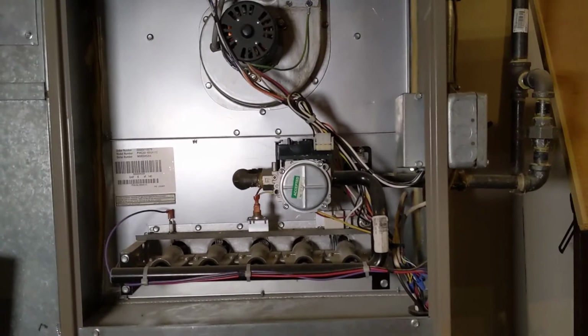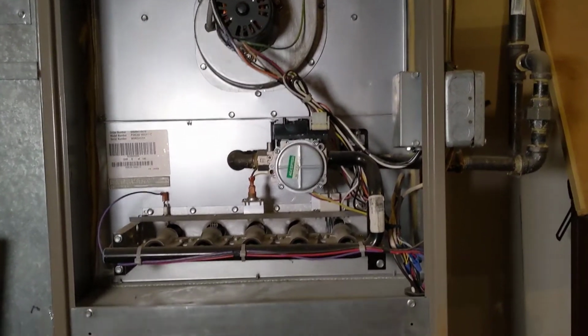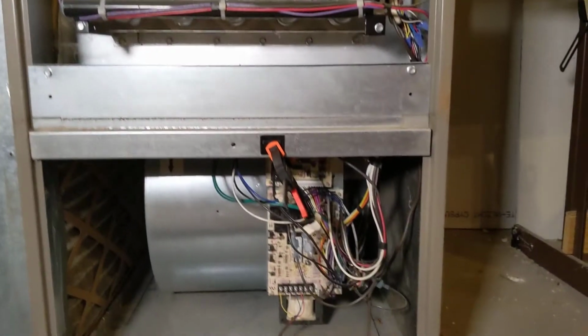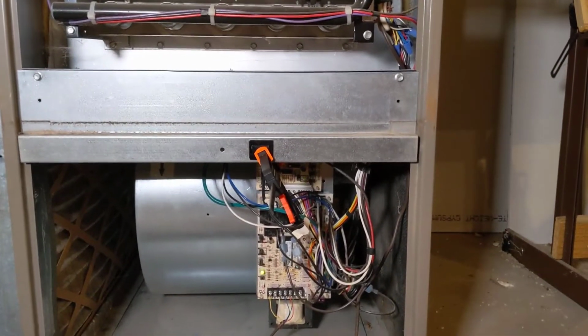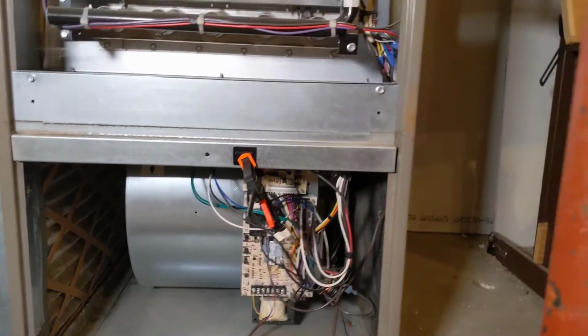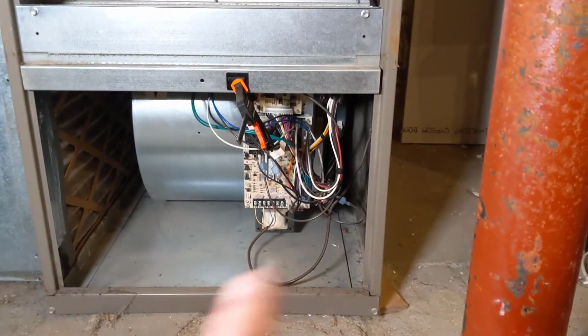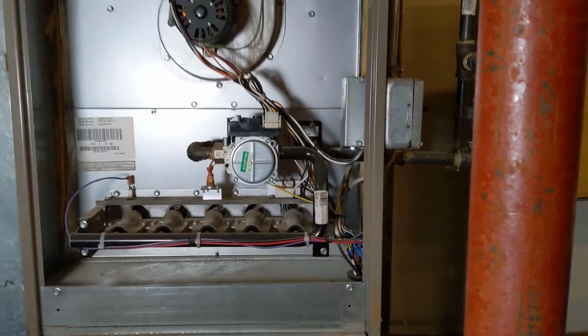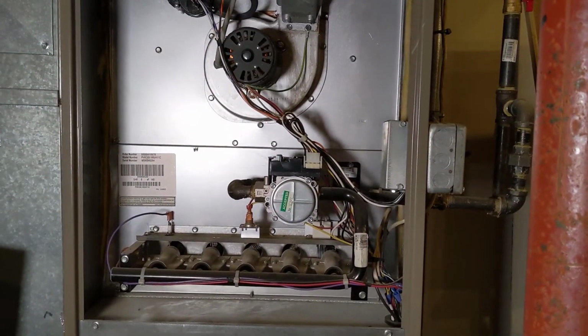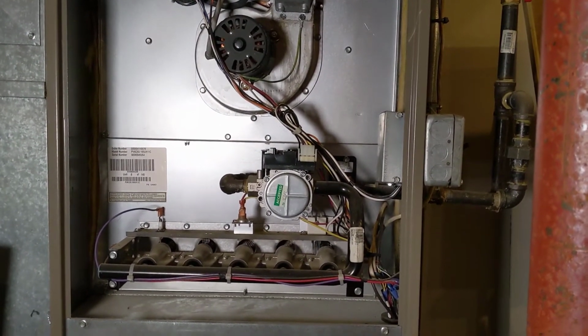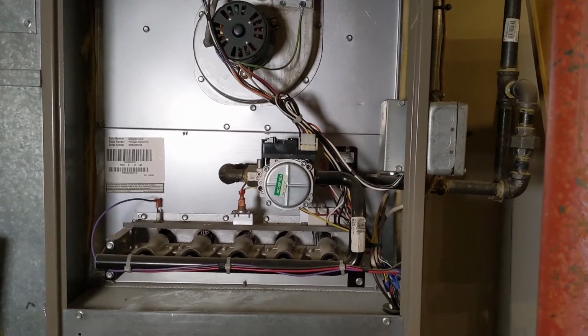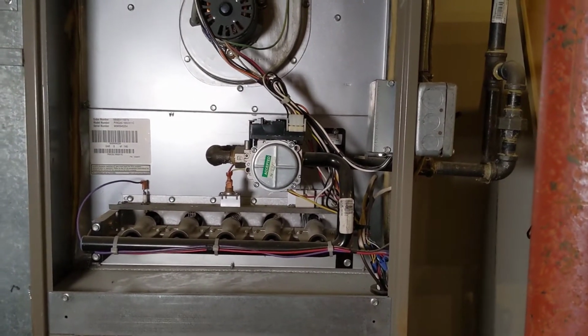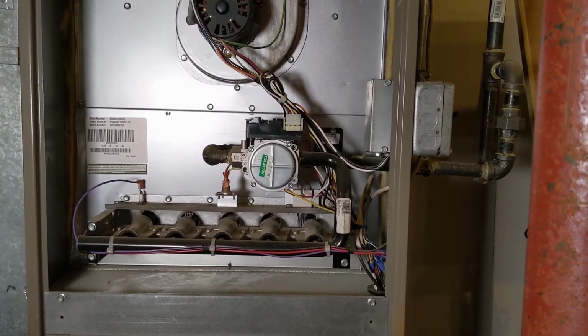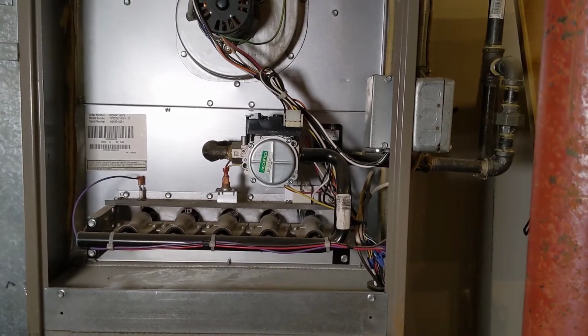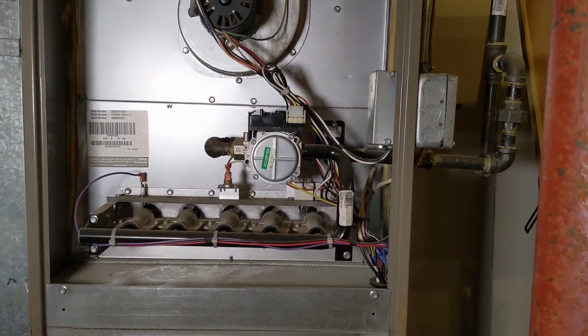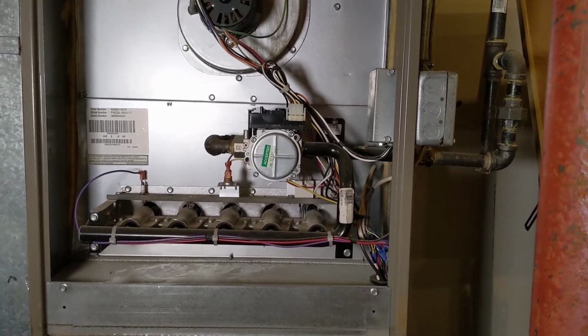So if we get to this point, we know that we have power and gas and everything coming in. We know that there's power coming to the board, but the furnace still isn't firing up. The most likely candidate, I mean, it could be a bad board, but more likely what the problem is, the thermostat isn't calling and telling it to provide heat. So at this point, make sure that your thermostat's on, it has fresh batteries, and that you have it set to heat, and then you have it set to a temperature hotter than the room temperature.